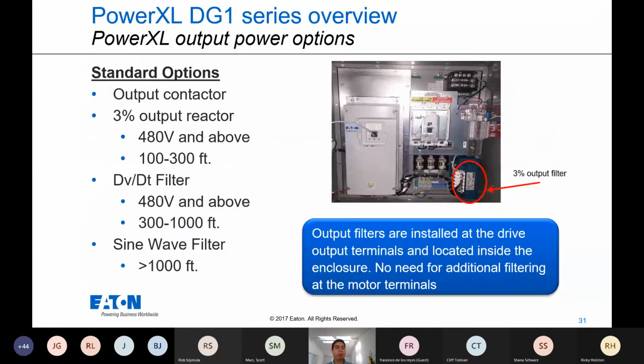Let's talk about the pulse width modulated wave, the recreated power wave that goes from your VFD to the motor. This also might require some special filtration, and these are some of the recommendations that we have. For a 3% output reactor, you can have good performance between 100 and 300 feet. A dV/dt filter when you go at 300 to 1,000 feet, and then a sine wave filter above 1,000 feet.